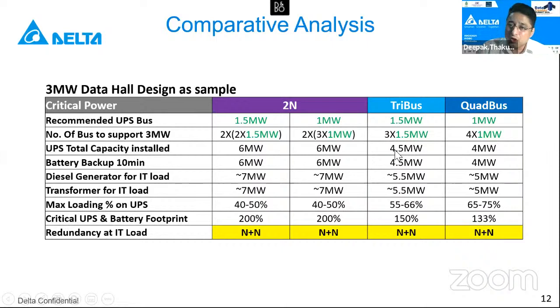So a lot, from 6 megawatts almost 2 megawatts has been written off in terms of capex on the battery sizing, as well as the battery cost and the space, and also almost 1 to 2 megawatts on the sizing of the other associated electrical hardware equipment and the capex. And also the OPEX is better because now you're running at 65 to 75%.